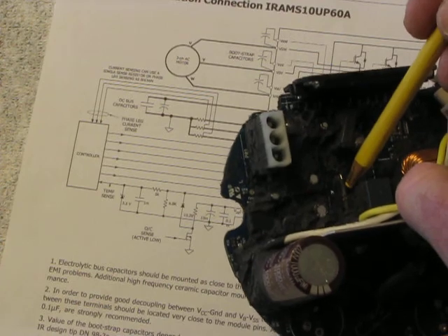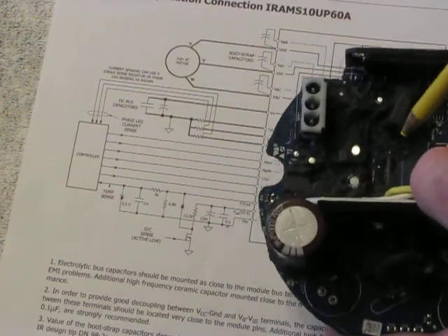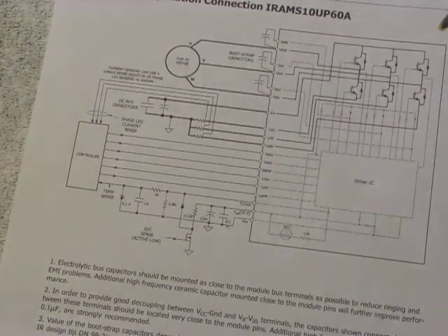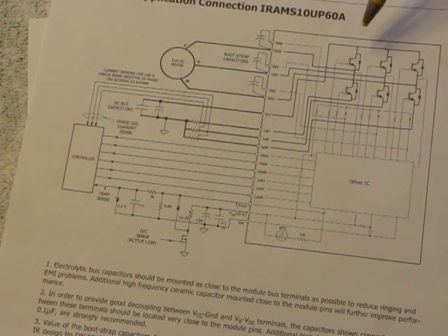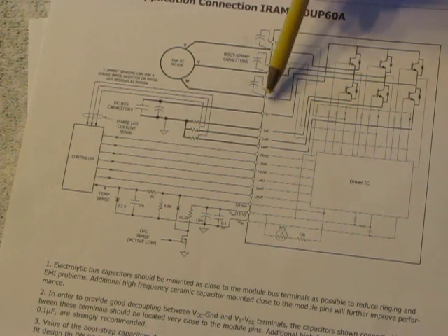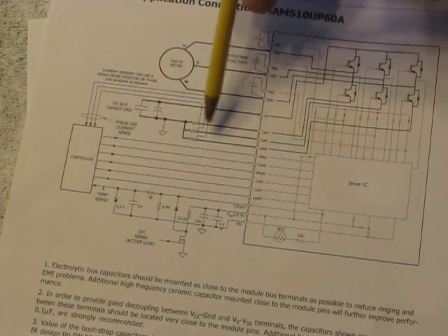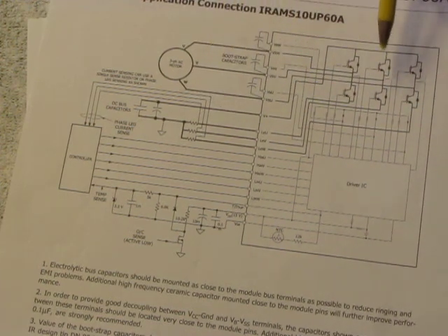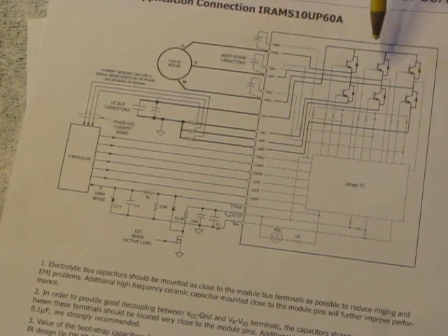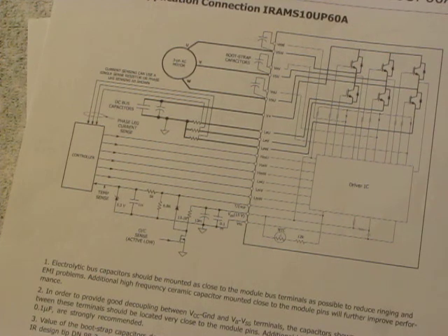There's one interesting thing. There's the resistor, the current shunt for measuring the current through the return on this IGBT array. And interestingly, this one failed because both these are shorted. So if you measure from the one side of this, where is it? Right here. Okay, that's 340 volts coming in, and then over here is the other side of the 340 volts DC. And if you measure from here across the 340 volts, or at these two points of this array, you get a short. And then also, if you measure this output, you get a short. So it's shorted from here to here to here. But these are okay. But it won't work with one.